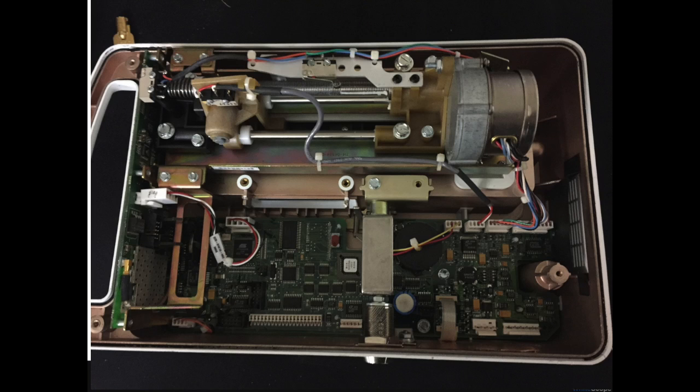If we remove that communications board from the actual pump, this is what it looks like removed. So I've taken it out of the pump. And so we can see the Wi-Fi adapter over there, and here's the processor. It's a system on a chip processor for this. It's an ARM processor. And so this board by itself essentially operates independently of the other pieces of the pump, right? So if you took this board out and powered it up and connected it to Wi-Fi or connected it to a wired Ethernet, it would actually work by itself. Now, it would expect other components to be there, and it will test to see if other components are there, but the reality is it'll power up and run by itself, which means that this thing has its own operating system and it has its own software.